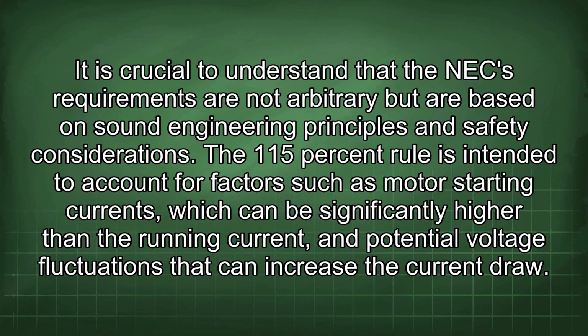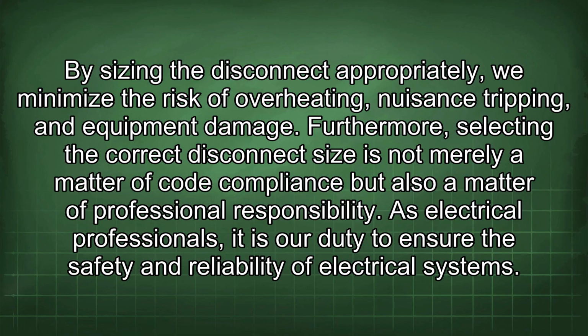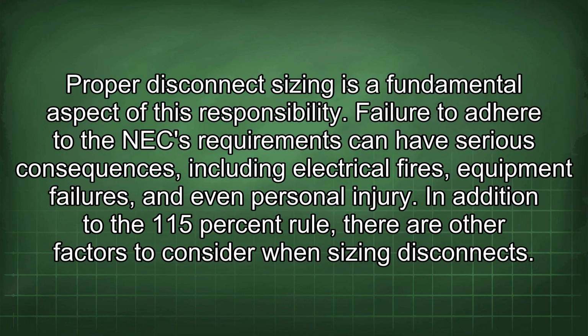It is crucial to understand that the NEC requirements are not arbitrary but are based on sound engineering principles and safety considerations. The 115% rule is intended to account for factors such as motor starting currents, which can be significantly higher than the running current, and potential voltage fluctuations that can increase the current draw. By sizing the disconnect appropriately, we minimize the risk of overheating, nuisance tripping, and equipment damage. Furthermore, selecting the correct disconnect size is not merely a matter of code compliance but also a matter of professional responsibility. As electrical professionals, it is our duty to ensure the safety and reliability of electrical systems. Proper disconnect sizing is a fundamental aspect of this responsibility. Failure to adhere to the NEC requirements can have serious consequences, including electrical fires, equipment failures, and even personal injury.